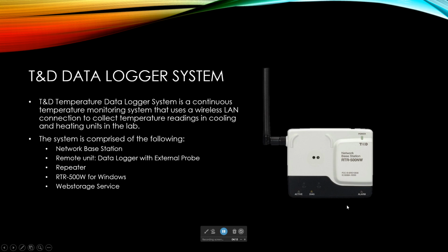So what are we using here? It is an instrument made by the T&D company, the T&D data logger system. The T&D temperature data logger system is a continuous temperature monitoring system that uses a wireless LAN connection to collect temperature readings in cooling and heating units in the lab.